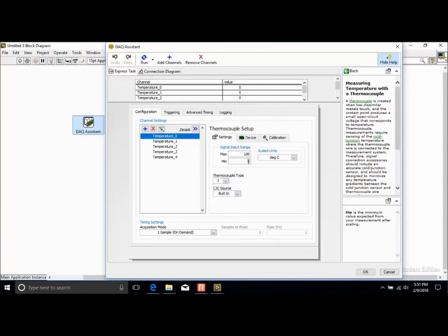We could bring this up a little bit. Our lab is a little hotter than typical room temperature. We could probably bring this up to 20, and maybe if you only decide to go up to 80, you could bring this down a little bit to try to reduce our range and get the best resolution possible. But this is pretty good for going from room temperature to up to 100.